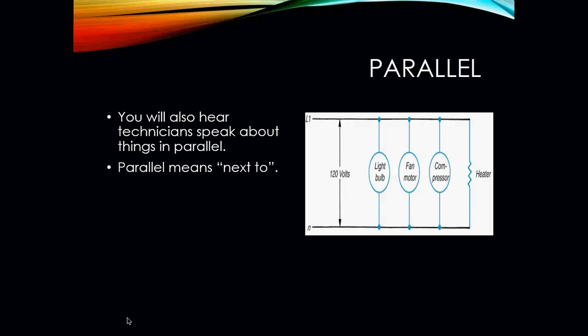So in a parallel circuit, each power-consuming device in that particular circuit is wired in parallel. For example, in this example here, say that this light bulb happens to break or die out. The fan motor would still get power, and the compressor motor would still get power. Why? Because each is still receiving its own power supply from start to finish. Our compressor and our fan motor will continue to operate, even if this light bulb is no good, it's gone.